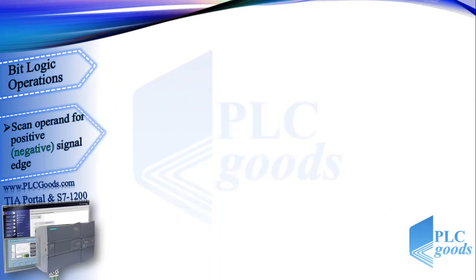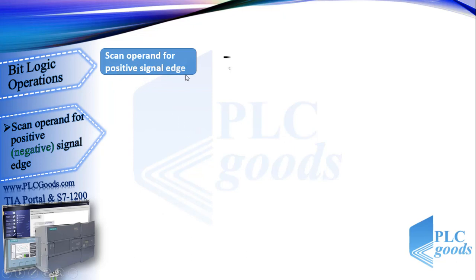Now let's see the first instruction: scan operand for positive signal edge. This is its ladder symbol. As you can see, this instruction needs two addresses. This instruction determines if there is a 0 to 1 change in the state of the I 0.0 address. These instructions need a bit memory address to work — here M 0.0 is used — and this is its FBD symbol.